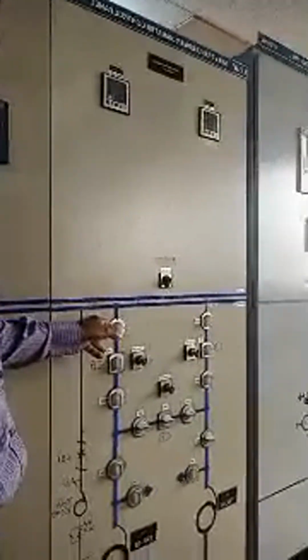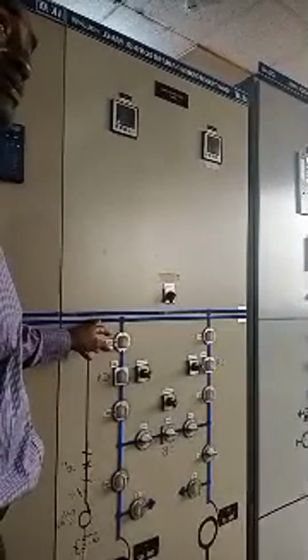That's how it is. Then on this side, on bus bar 2, this is the side that TR02 is. On this bus bar, near this transformer TR02 extended, you will see that our T3A is connected from this point. That's why if anything happens to bus bar 2, T3A also is affected. Is that right?